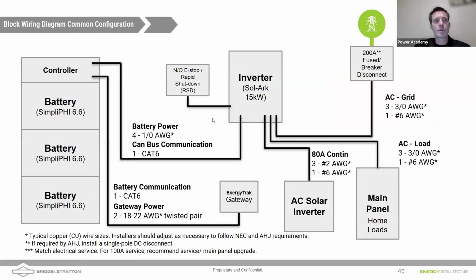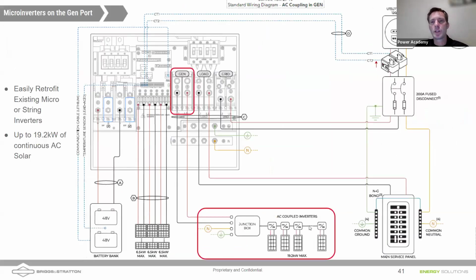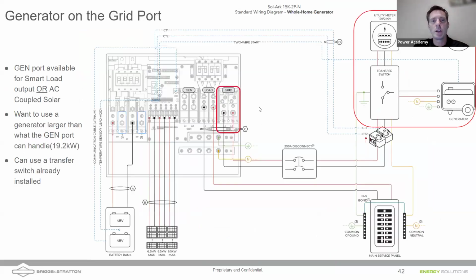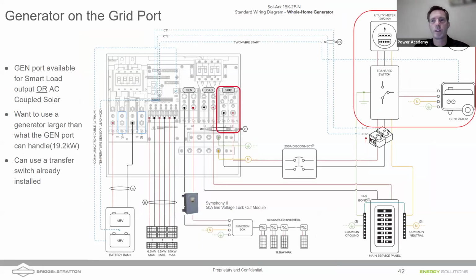We looked at this before, but this is showing you where you would bring that AC solar microinverters in, through that gen port on the inverter, and we need to be able to configure that to run appropriately. So on the multi-line diagram, you can see here that we'd be bringing these microinverters up to 19.2 kilowatts. That probably wouldn't bring in that much AC coupled solar, but I've done systems with, I think we did one here with 16K of AC coupled solar, and it works just fine, right? The Sol-Ark does a nice job of using AC coupled solar to charge the batteries and keep the home alive. The other thing we can do is, of course, bring the generator in on the grid port, but I think this is just a...